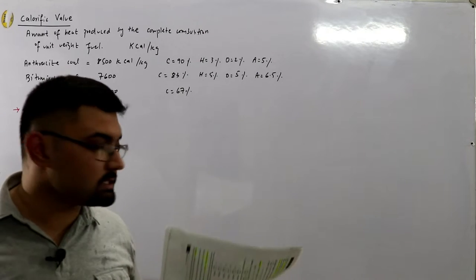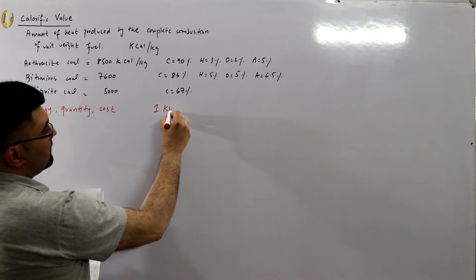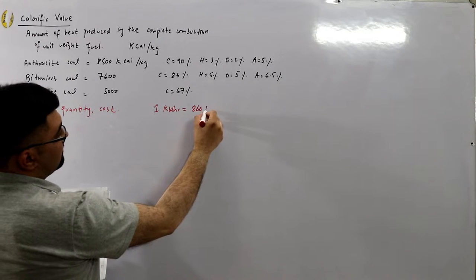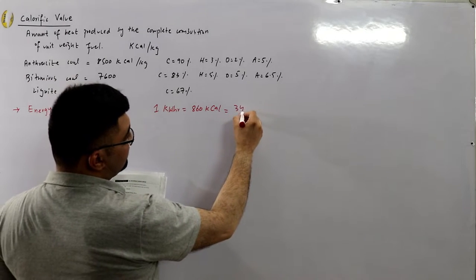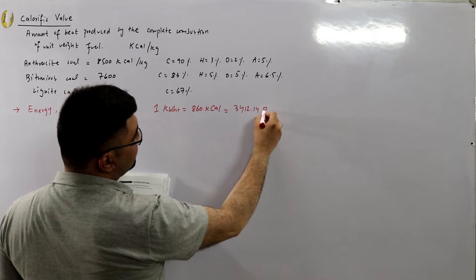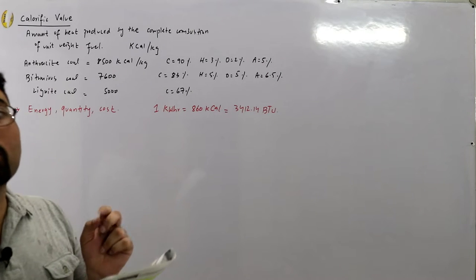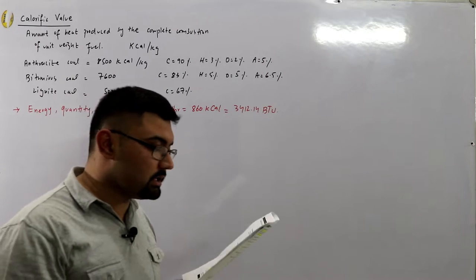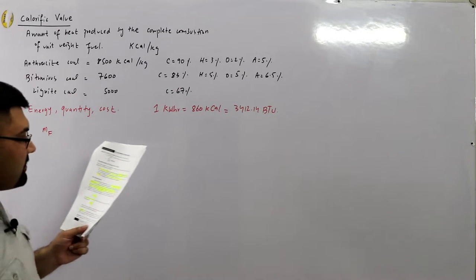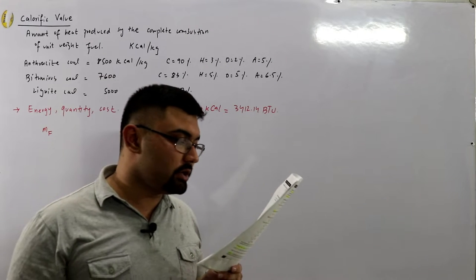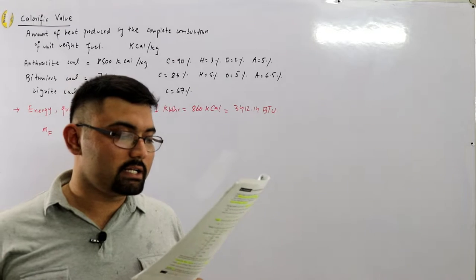The heat energy equivalent of one kilowatt hour of electrical energy is 860 kilocalories, which is 3412.14 British thermal units. The quantity of fuel, represented by mf (mass of fuel), can be determined by knowing the energy content of the coal in kilocalories per kilogram — that is, the calorific value or higher heating value.